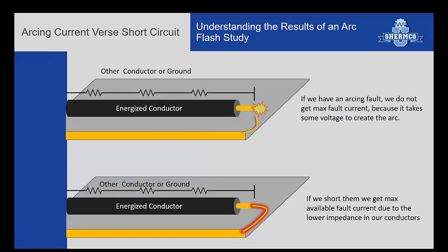Okay, so we want to talk a little bit about arcing current versus short circuit. Arcing current is what's used in the calculations of how quick the breaker is going to trip. Arcing current is not the same as short circuit, because in a short circuit, if you have a dead short, the amount of current is really limited to the impedance of the conductors.